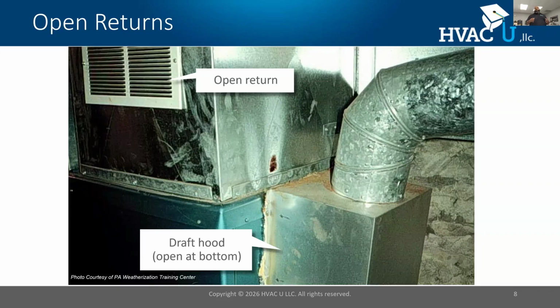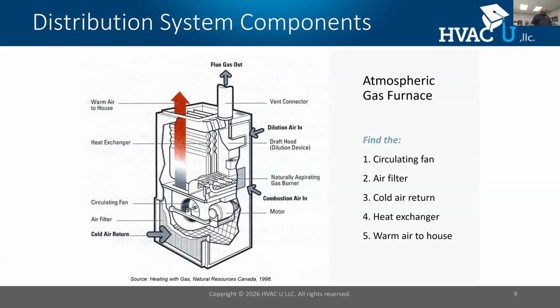And when we look at the house as a system, this return air, which was trying to relieve the furnace from short cycling off on a temperature limit, was actually overcoming the exhaust gases in the flue piping. So it's highly important that the ducts not only be done for efficiency purposes and comfort, but if we make a mistake like this, it can also be harmful to the occupants.